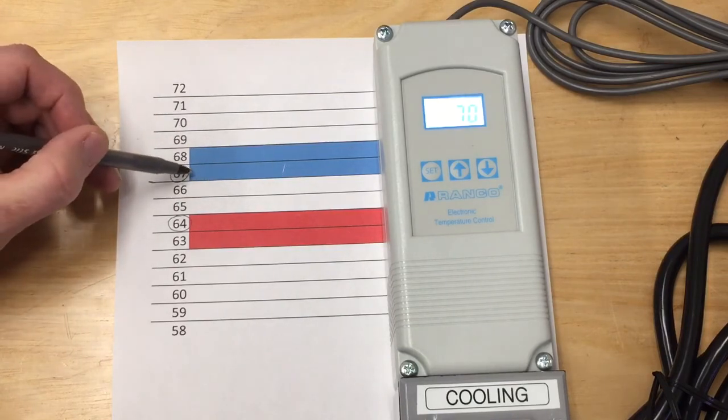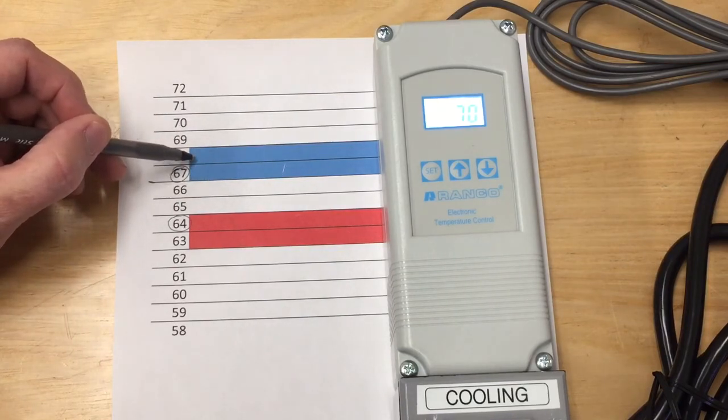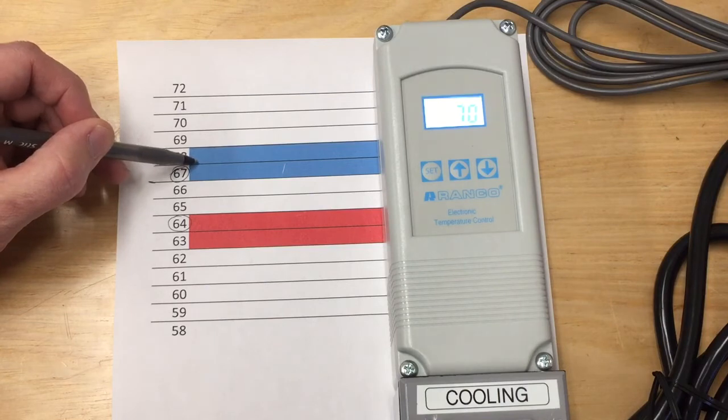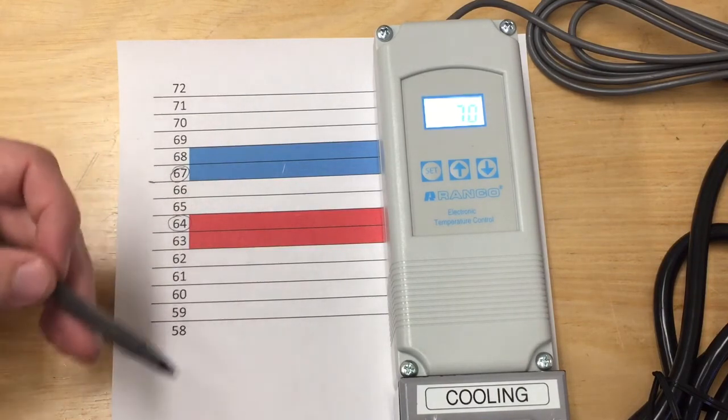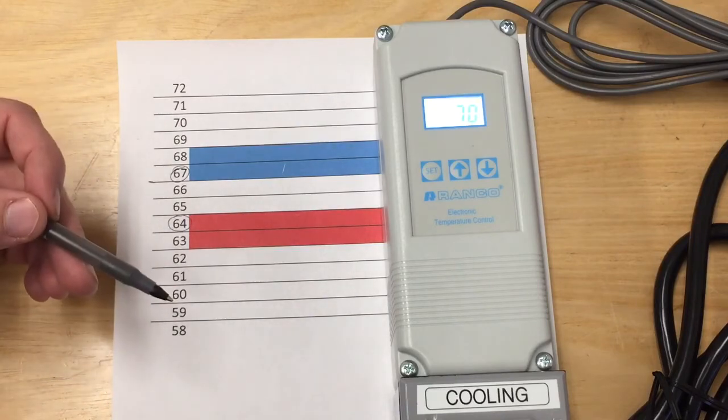A one degree differential at 67 would turn the refrigerator on at 68 and then off as soon as it's back to 67. That can cause a lot of cycling and issues with compressors.